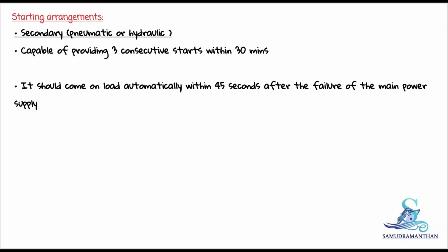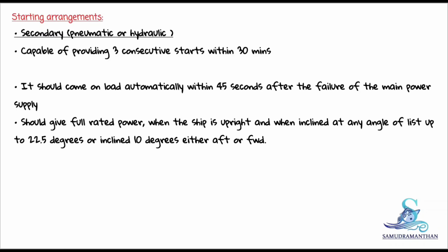It should come on load automatically within 45 seconds after the failure of the main power supply. Should give full rated power when the ship is upright and when inclined at any angle of list up to 22.5 degrees, or inclined 10 degrees either aft or forward.